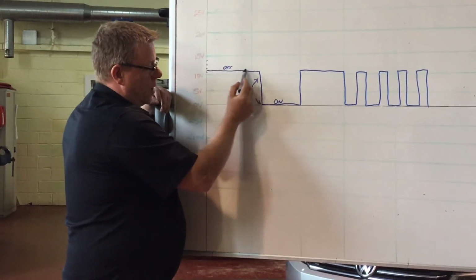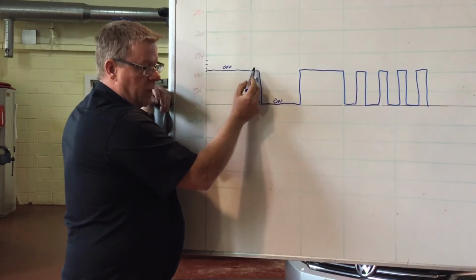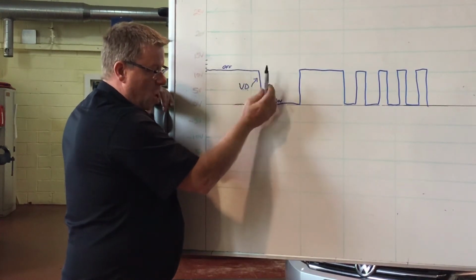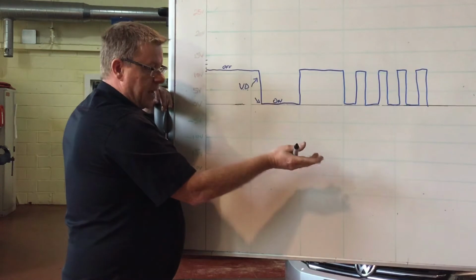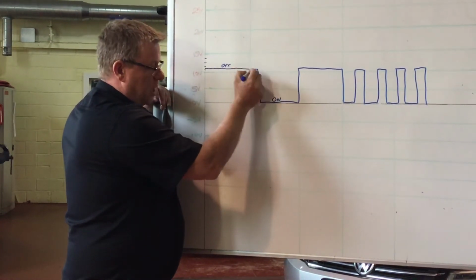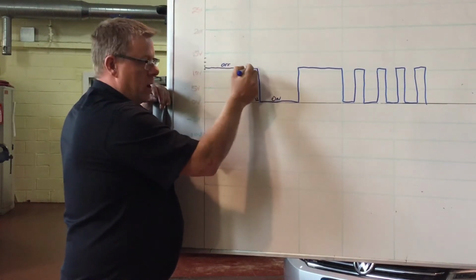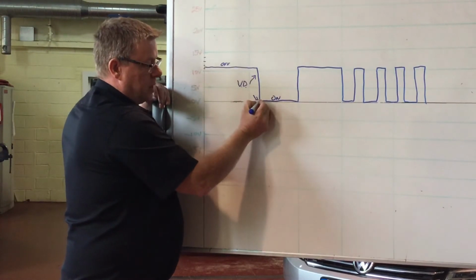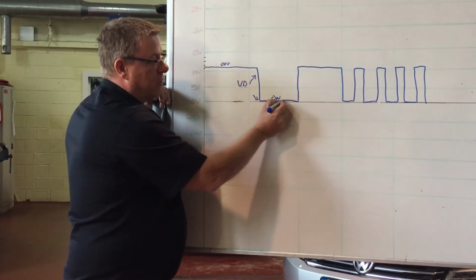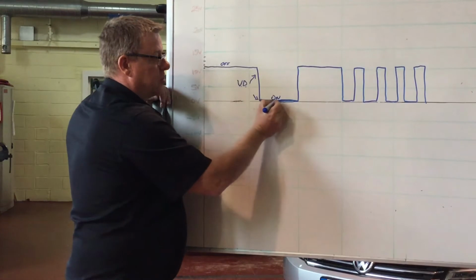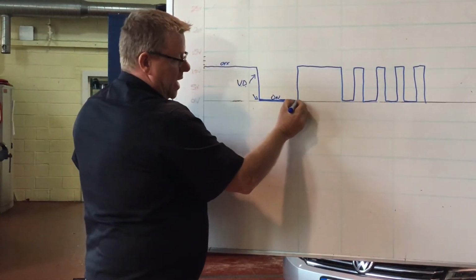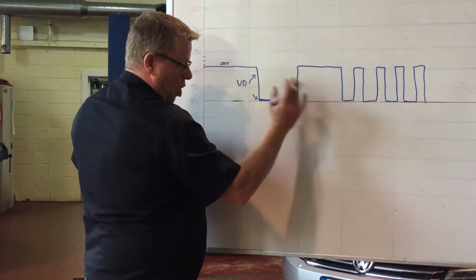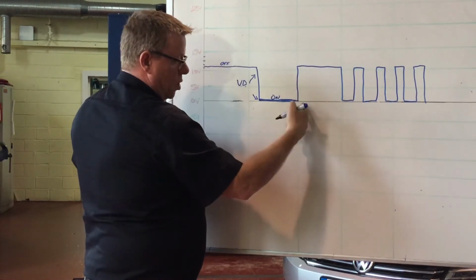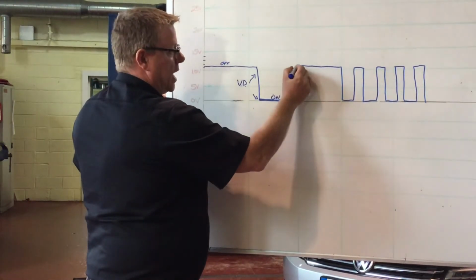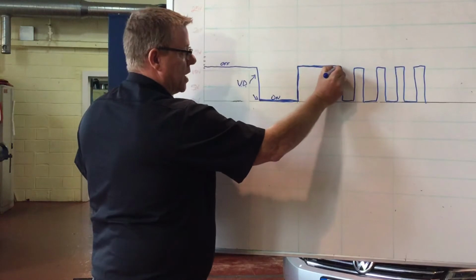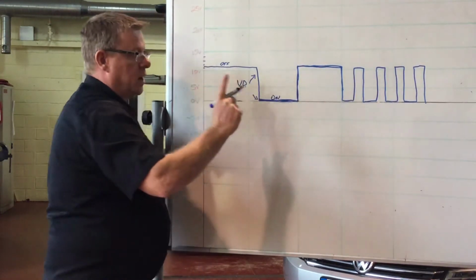So we were off here, circuit switched off, and the earth switch is in an open position. Then we connect the circuit to earth, which means because we're probed on the earth side, where our probe is suddenly became an earth, but that is actually on for us here. So we're on here now when we're dropped down here. Again, we broke the circuit, so we opened the switch on the earth side, which meant our probe is still connected, and now we're back onto the positive side here, and off we go again. We see on, off, on, off, on, off.